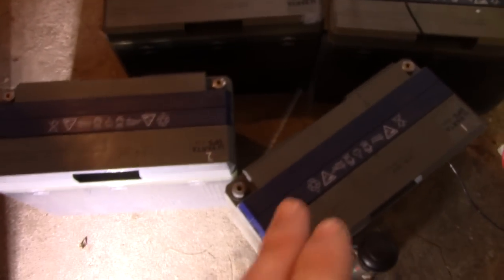This particular battery looks really great. There's no sulfate on the positive plates, and the negative plates tend not to get many problems in comparison. So this one's really great, as well as this one — and they are the newest of the batch. These are from 2003, however these three back here are from 2001 and they seem to be a slightly older revision.